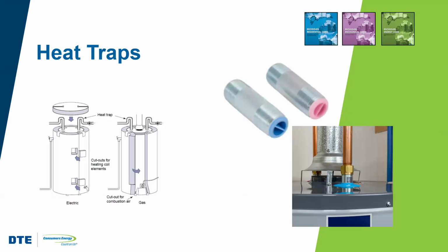This is a criterion on the commercial side, not necessarily for the residential side just yet, but it's still a good idea. Heat traps help improve the efficiency of the system and reduce wasted energy. They minimize heat losses, just like the check valve in the hydronic system. They prevent that sort of thermal siphoning, right? Newer water heaters often come with these already installed, but they can be added to existing systems. Sometimes you'll see older existing systems that had this loop in the piping. That's a form of heat trap, right? But newer systems will have these valves installed, and they're color coded so you can tell which one goes on the cold side and which one goes on the hot side, and you can see the color coding here on the unit as well.